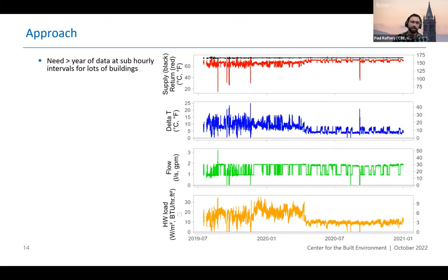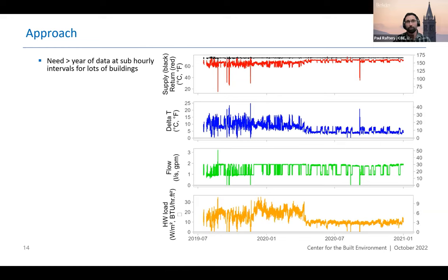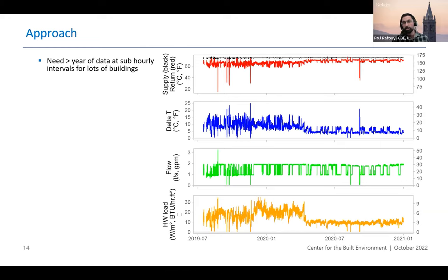What we need to do this is basically lots of data — at least a year, preferably several years of data at five or 15 minute intervals from hundreds of buildings. We're essentially seeking out supply and return water temperature and flow so that we can actually measure things like delta T and the hot water load on the actual system. We also gather lots of other information like pump speeds, differential pressures, and firing rates, but supply temperature, return temperature, and flow are the essentials. No public data set exists for this, so we had to go out and create one — a really mammoth task.